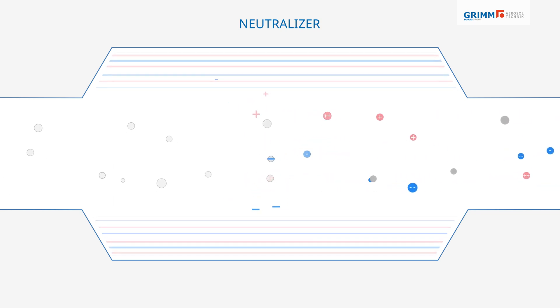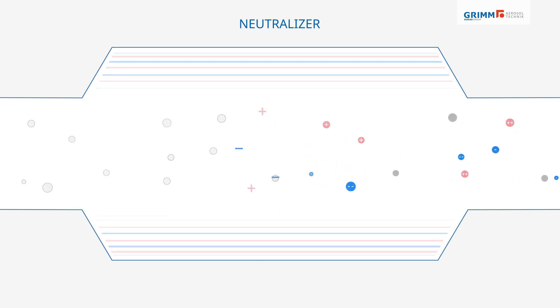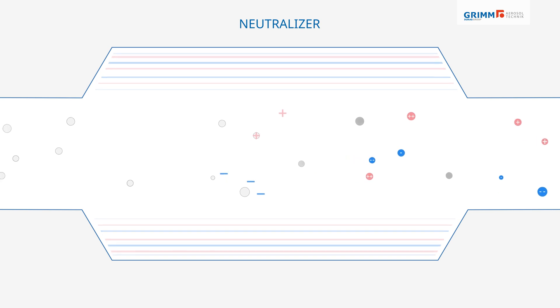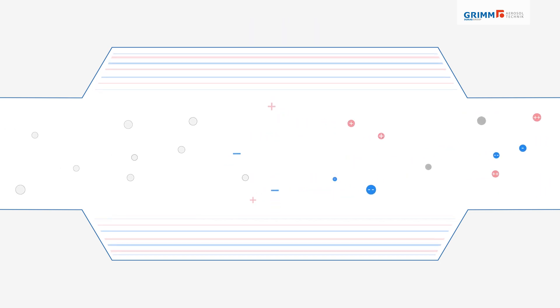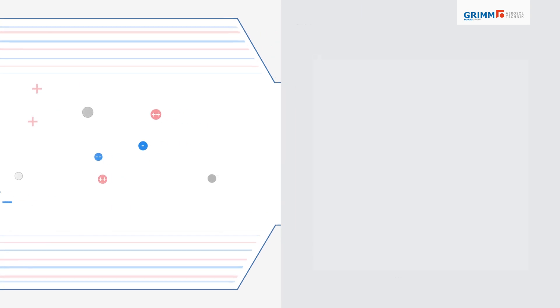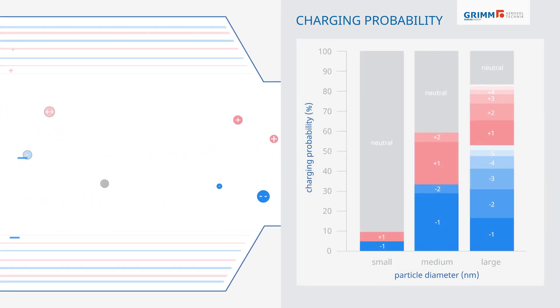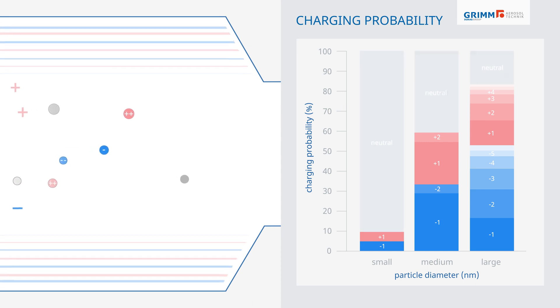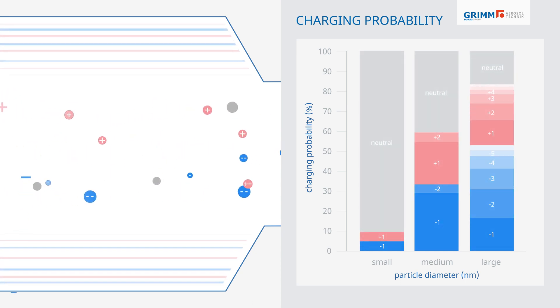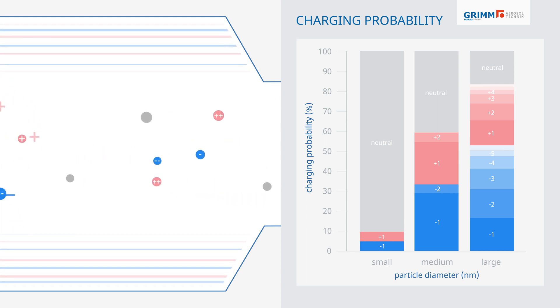Neutral, positive and negative particles are the result. A known particle charging probability is the basis for later corrections of the particle size distribution. This probability distribution shows how many neutral, positively and negatively charged particles may be included in a size class.